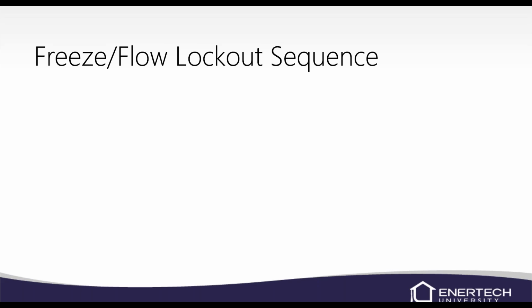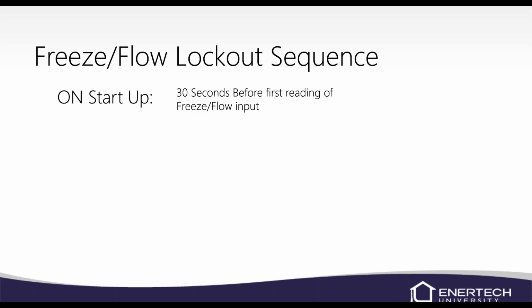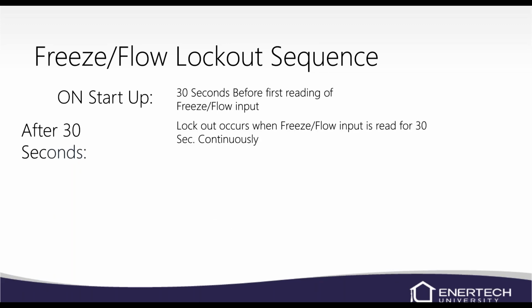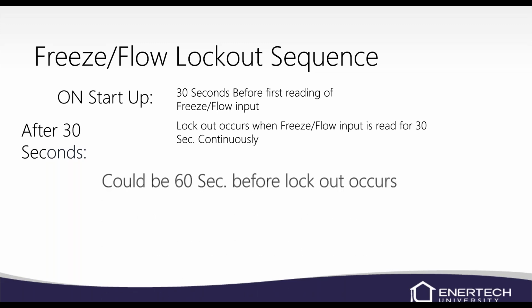A freeze or a flow lockout, that's going to depend on a couple things, how you have your board set up, whether it's looking at a thermistor or a flow switch. So we'll come back to that here in just a minute. On startup though, it will not monitor the freeze or the flow input for 30 seconds. Again, it's allowing your pumps to come up to speed and get up to full throttle before it monitors that. After 30 seconds, the flow switch or the thermistor has to be open or sensing a temperature outside of its range for 30 seconds. So it could be 60 seconds before the unit locks out on a freeze or a flow lockout.